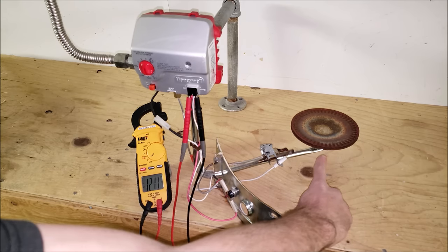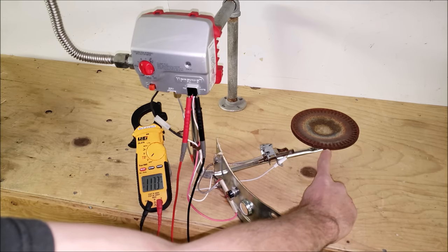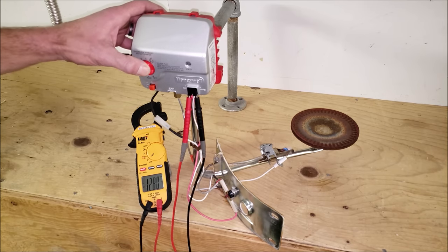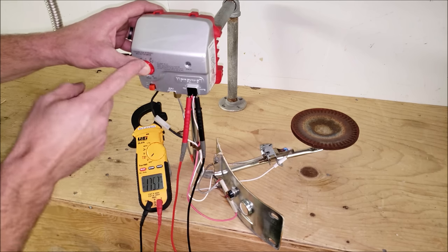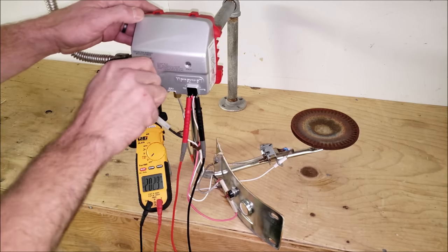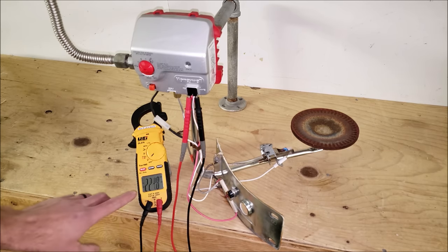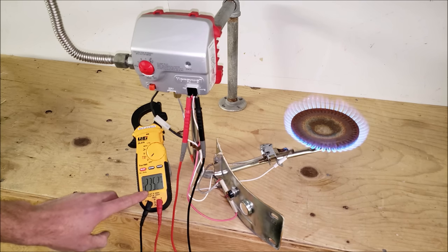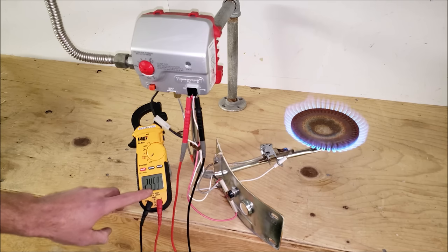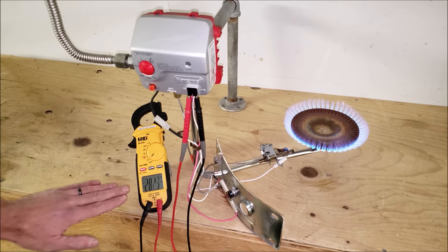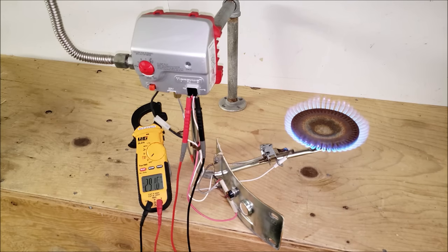Now we're going to see what voltage it takes for the main burners to turn on and for them to cut out. Let's go ahead and relight our pilot. As soon as we have enough DC millivolts to hold this pilot valve, I'm going to turn the main burners on. There it is. So we're at 215, 235, so right about 260 you saw is when the main burners lit and then they actually dropped down about 30 DC millivolts while the load was occurring and now we're still climbing because our thermopile is continuing to heat up.